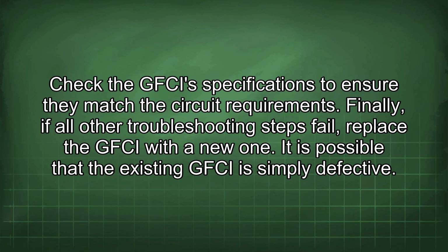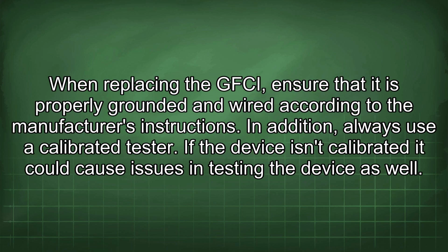Finally, if all other troubleshooting steps fail, replace the GFCI with a new one. It is possible that the existing GFCI is simply defective. When replacing the GFCI, ensure that it is properly grounded and wired according to the manufacturer's instructions. In addition, always use a calibrated tester. If the device isn't calibrated, it could cause issues in testing the device as well.